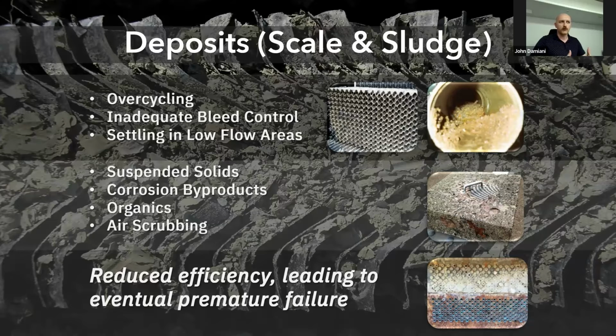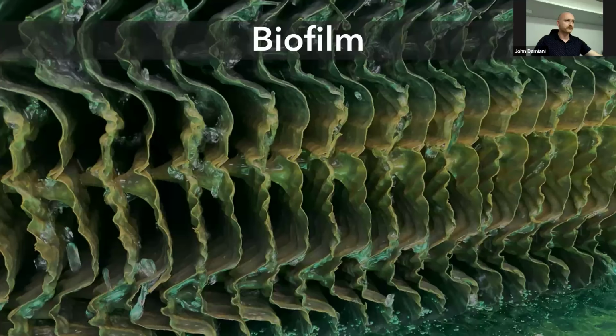So we're impeding the heat transfer because we don't have a clean surface anymore, and that's going to reduce our efficiency up front. And then over time, if not addressed, if we're plugging tubes or if we're really gumming up the system with fouling, that can lead to eventual premature failure.